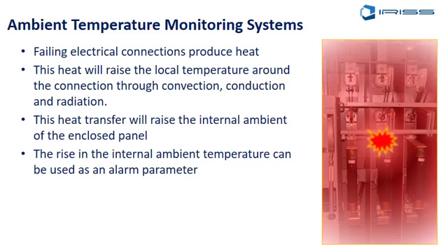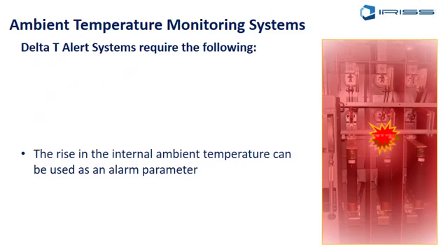They're very simple. It doesn't matter how many connections there are, just one connection can raise the temperature of a panel relatively quickly. Although they're smaller rises in temperature, we can set the alarm parameters quite tight to pick up these small ambient rises.